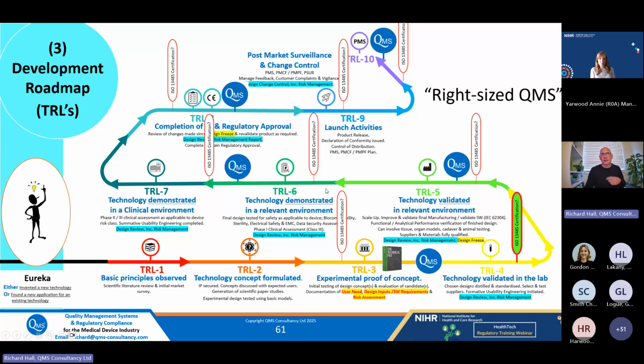TRL6 is where you would check the safety of the product. This is where you might do phase 1 clinical assessment for a class 3. You might check electrical safety, sterility, data security for anything connected to the internet. And that's all done on stuff that you've manufactured in your validated processes. Then you do clinical performance testing in TRL7 on stuff you're about to place on the market. Generally speaking, in TRL5, you might make more than you need, and that stuff goes onto the market in the future. So you're testing to make sure it's okay.